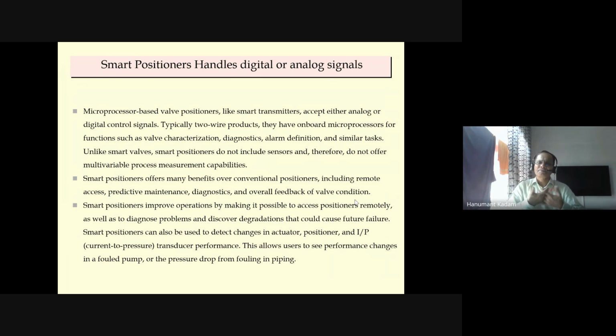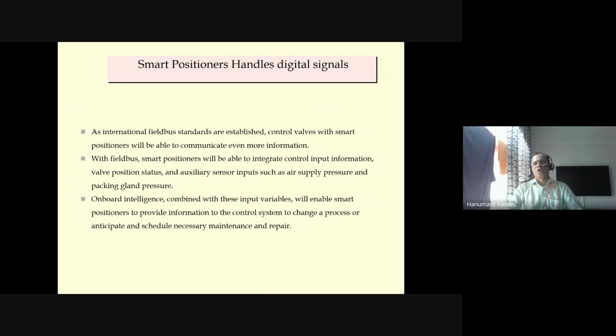Because of these crucial inputs, you can detect equipment damage in the line, like a pump or pipeline. Because in pumps and piping, due to corrosion, some foreign particles get choked in the valves, and you will come to know, due to the smart valve positioner's pressure measurements. So that is what is mentioned. I have explained how these new technologies, like Fieldbus, help with predictive maintenance.